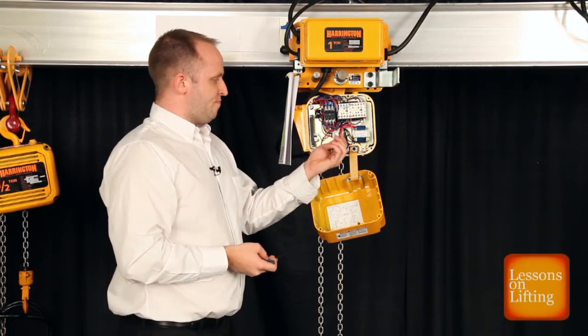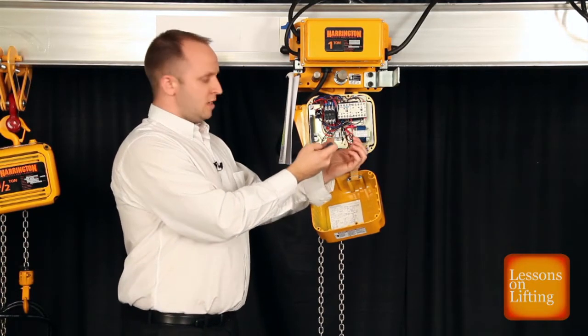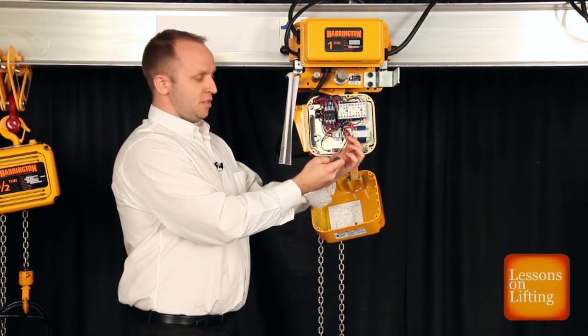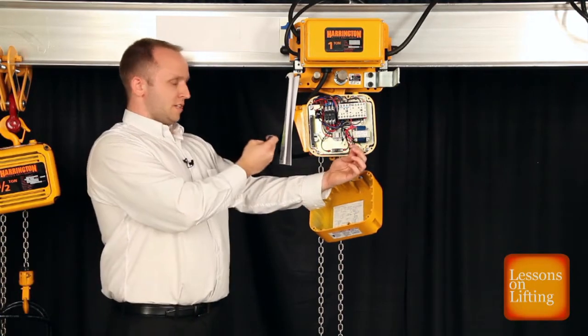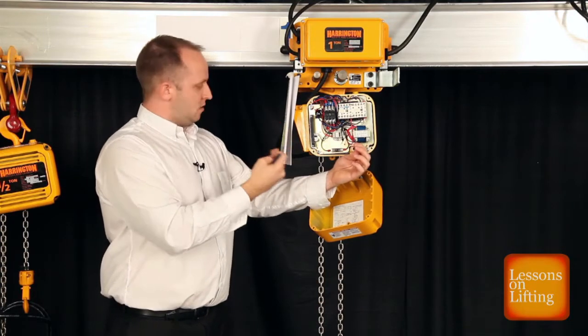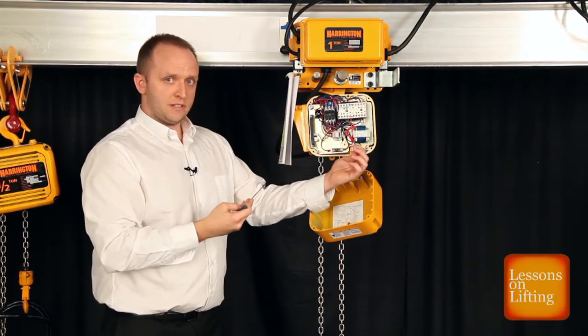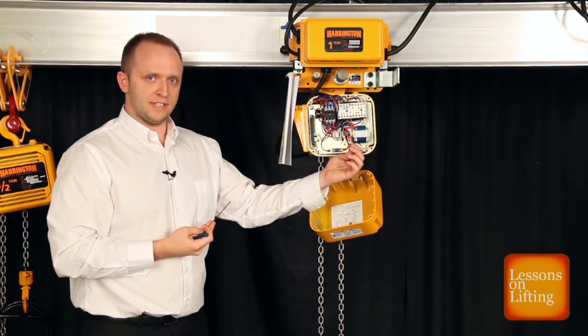So from this point, I would identify which wire, pick one, identify the label on it, this one happens to be U1, reference the configuration on my wiring diagram that I need to end up with, and attach that where the diagram tells me to. And I'll do that for all four wires, and then we'll be ready to move on to the next step.